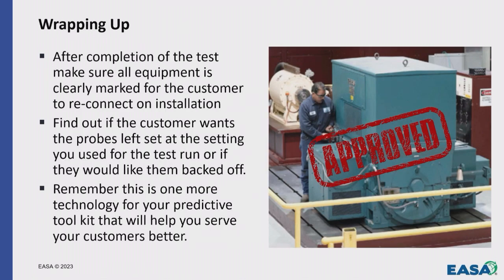Wrapping up, make sure your customer is happy with the test results, and you've been in communication with them the whole time. Find out if the customer wants the probes left set at the 10 volts or 8 volts is the other common one that we get once in a while. Find out if they want the probes left set there, if they want them backed off.